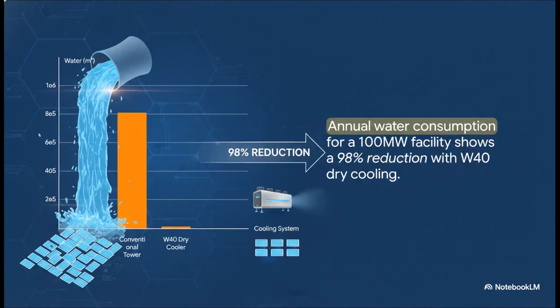First up, the water savings are staggering. A conventional tower system guzzles over 800,000 cubic meters of water a year — enough to fill more than 320 Olympic-sized swimming pools. The new W40 dry cooler system sips less than 15,000. We're talking a 98% reduction, down to the equivalent of just 6 swimming pools.